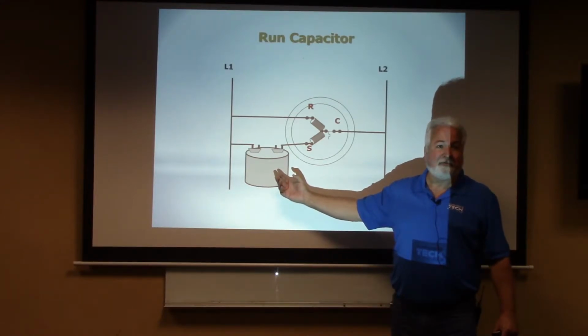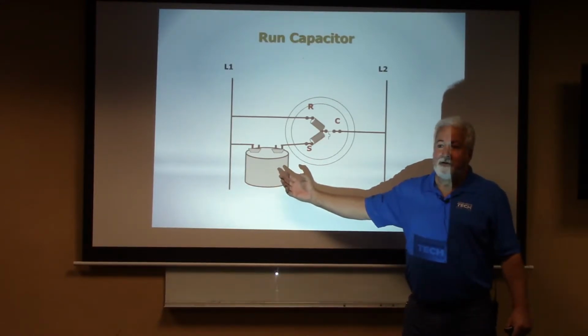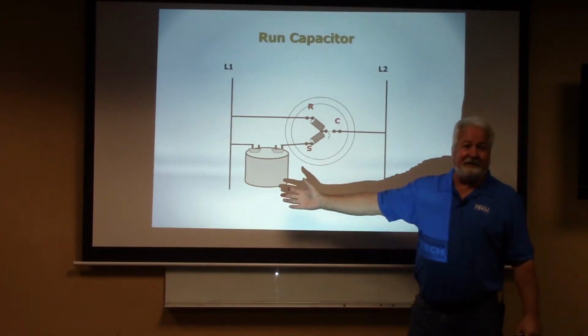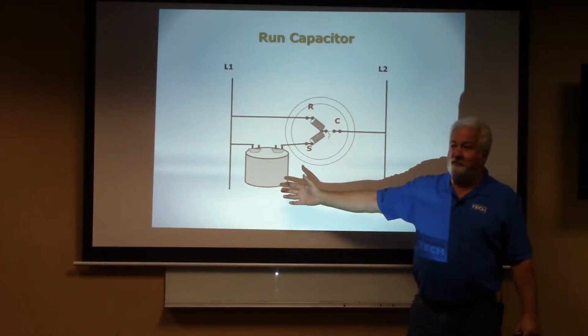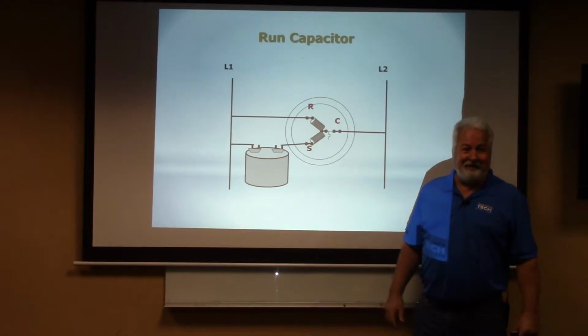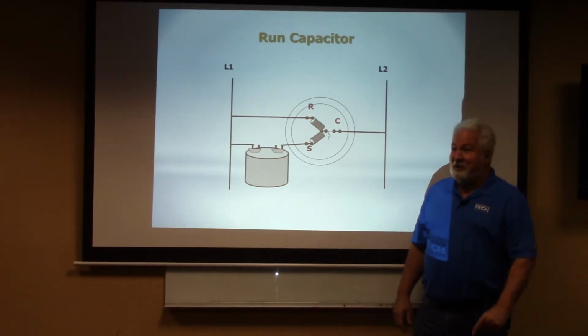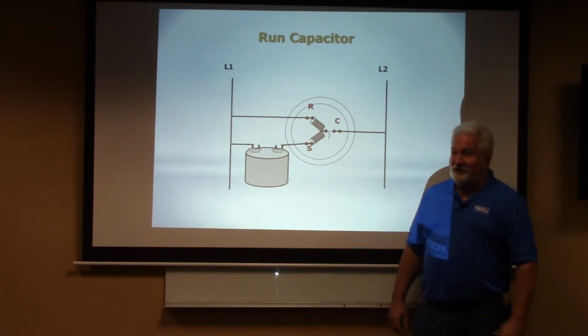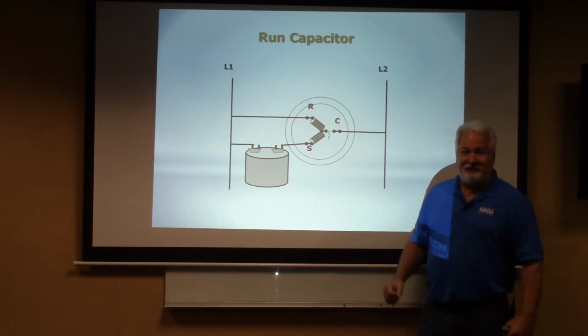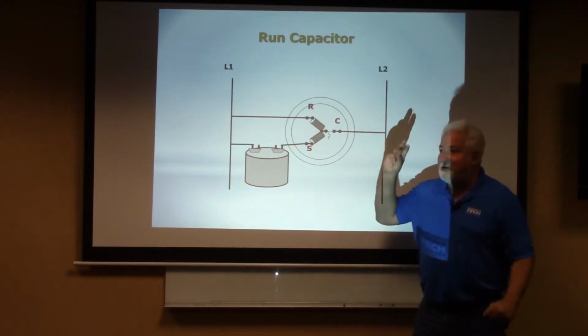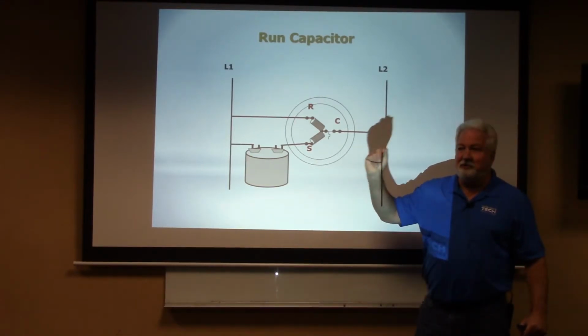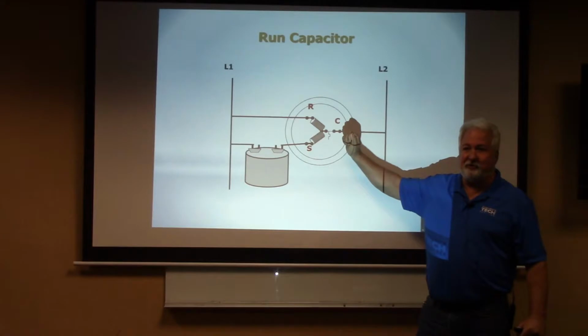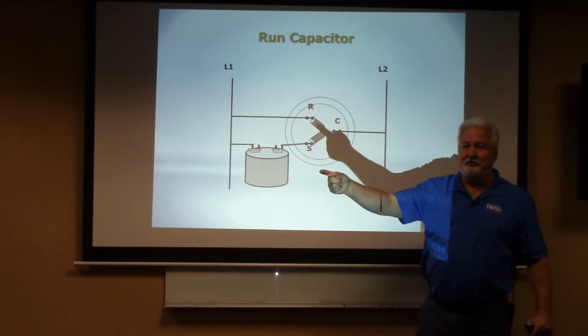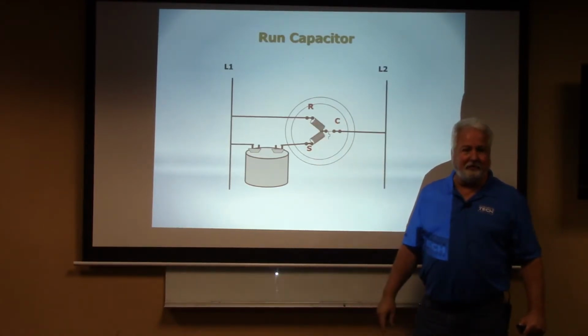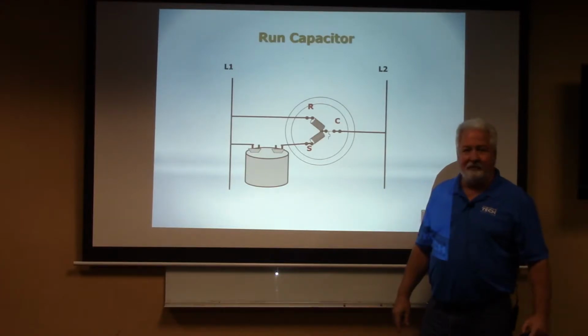To start up, what's the first thing that start winding sees? Boom! Huh? What just happened to my little capacitor buddy? He ate his spinach. He's Popeye. He just ate his spinach for that millisecond to be able to throw that high voltage to that start winding to be able to get that direction and that starting torque to make it happen. Is everybody good with that?